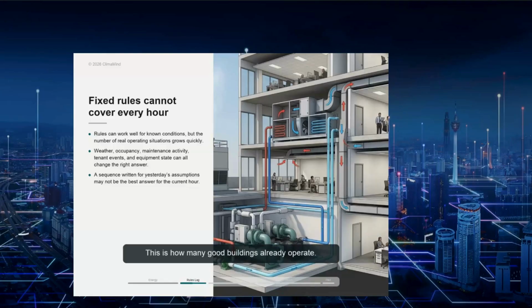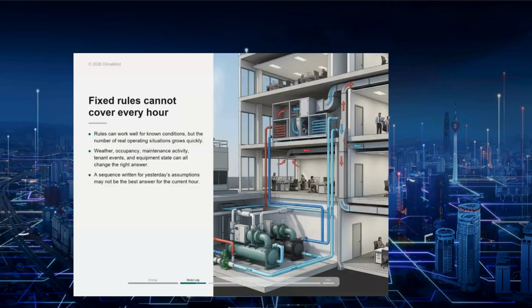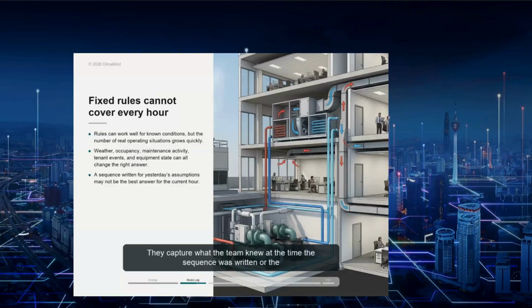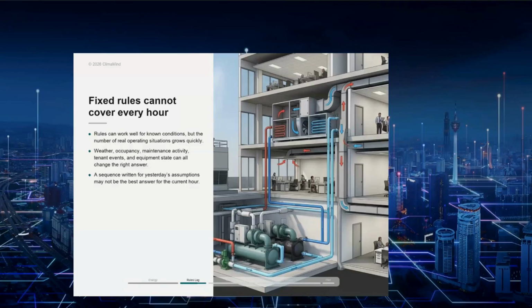This is how many good buildings already operate. They have schedules, sequences, set points, and overrides. They may also have periodic commissioning or retro-commissioning work that brings the building back into a better state. All of that is valuable. None of it should be dismissed. But those methods are still mostly static. They capture what the team knew at the time the sequence was written or the building was tuned. They do not continuously ask whether the current hour is different from the hour the rule was designed for.